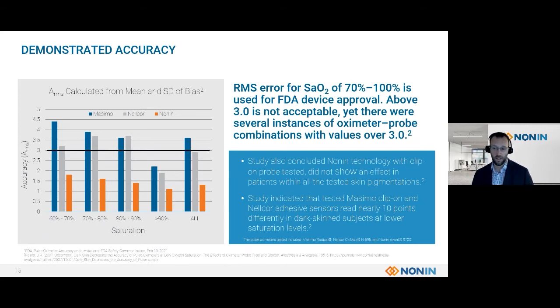But focusing on the Nonin PureSat oximeter with the clip sensor, this was more accurate compared to the gold standard, or blood gas, throughout the oxygen saturation levels for all skin pigmentations. Nonin was actually the only clip fingertip oximeter that provided accuracy readings of ±2 for tested individuals at all saturation levels, regardless of skin pigmentation, which is below the FDA acceptable limit. This study concluded that the Nonin technology with the clip probe tested did not show any effect of skin pigmentation in patients with all skin pigmentations tested.